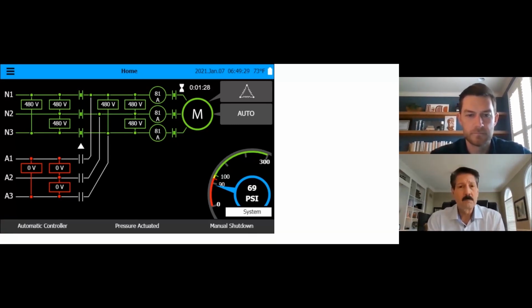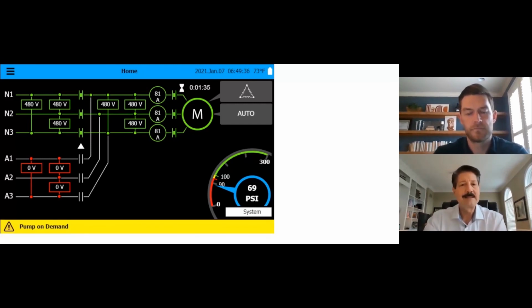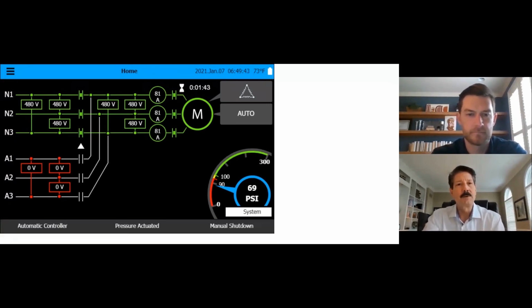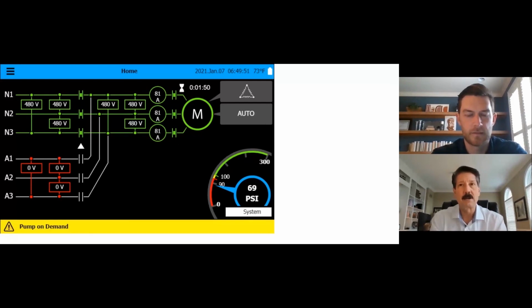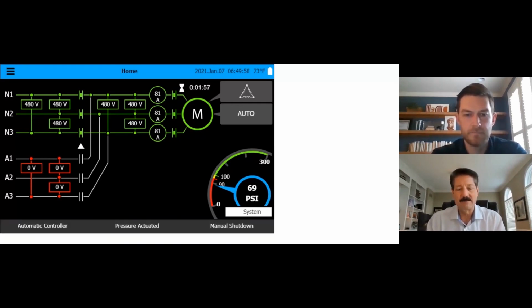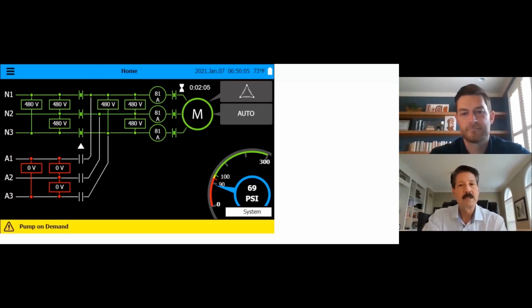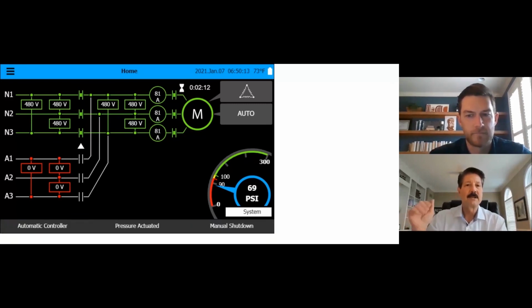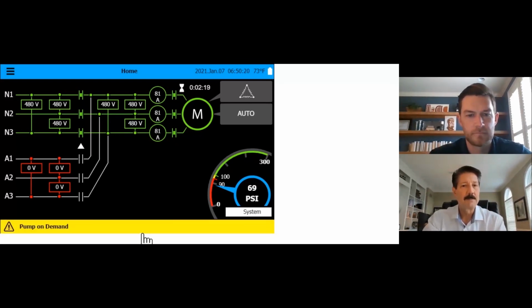Number two, well, you have a main break. Something could be a tow motor runs into one of the pipes somehow accidentally, causing a main leak in the fire system, and it could be many different things. Another reason, we've actually had people that open up valves that shouldn't be opening up valves, thinking that they could just tap off water for a variety of different things, making concrete, washing trucks, having the ability to reduce the size of that valve and spray things down with a hose. There's just so many of them. I'm sure you could add to the list too. So again, there's really only a couple things. And the last major thing is your system pressure dropped because you got sprinkler heads open and you have a fire. So it's got to be one of those. But this is really the only time you'll ever see pump on demand auto.